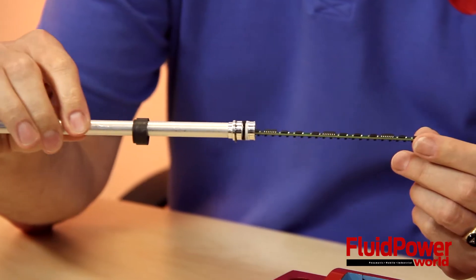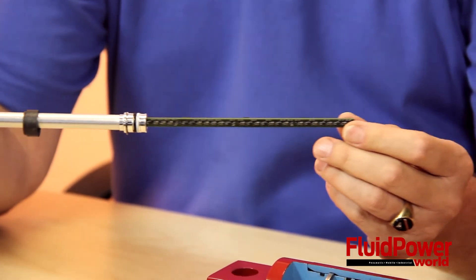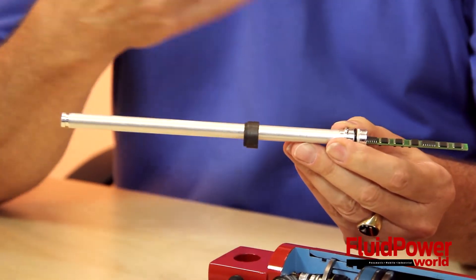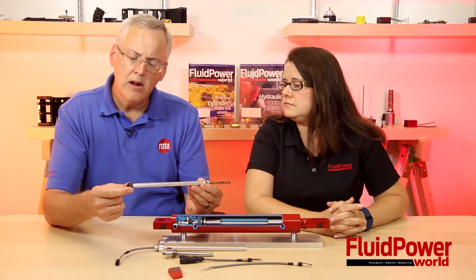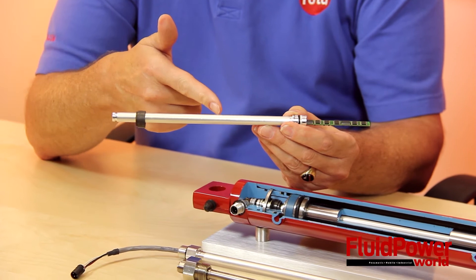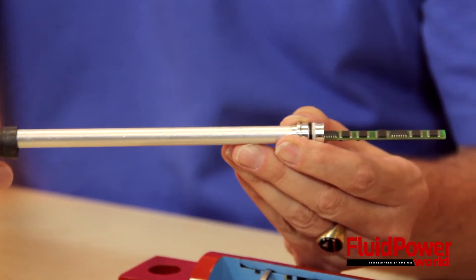All of our technology that I work with is based on Hall Effect technology. The PC board is where the Hall chips live, and then they're placed inside of the mechanical package, be it aluminum or stainless steel, just depending upon the application. We just need two components to make this technology work: we have the sensor and we have the magnet. The magnetic field communicates with the Hall chips internally and causes them to give an output that the microprocessor understands, and then it converts it to something that's current output, voltage, or digital — something specified for the customer's application.